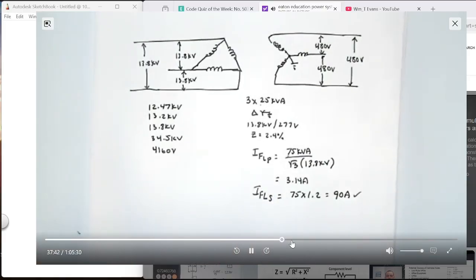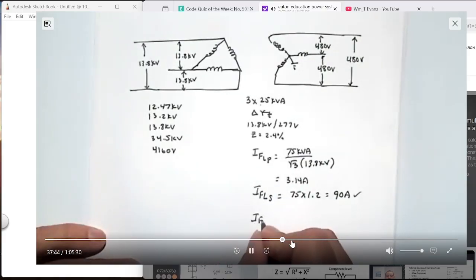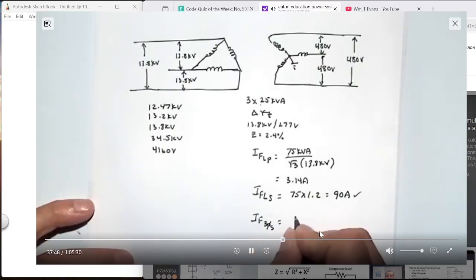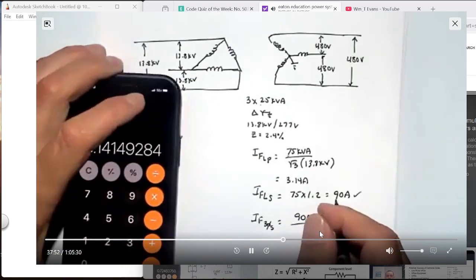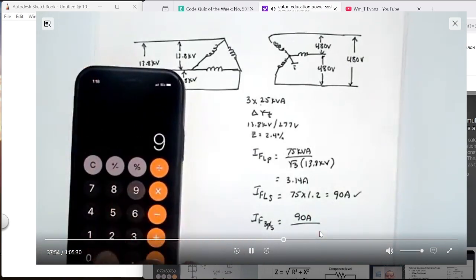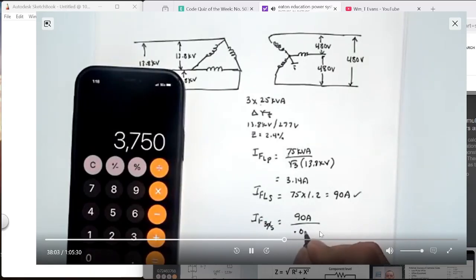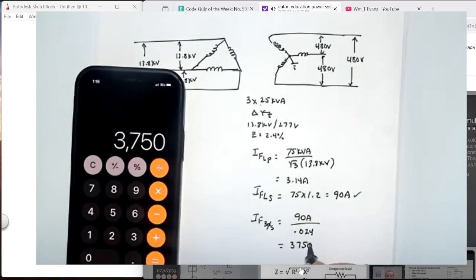Now let's calculate our fault current. So I fault 3-phase on the secondary is going to be 90 amps divided by our impedance. And again, the impedance for these is typically pretty small. So we're going to use the number on the nameplate in this one, 0.024 per unit or 2.4%, and that works out to 3750 amps of fault current.